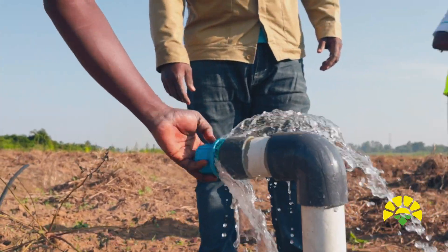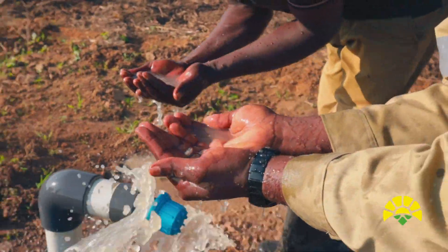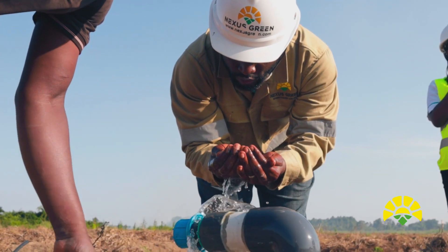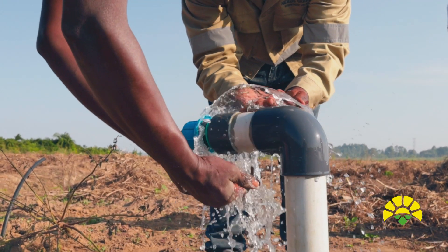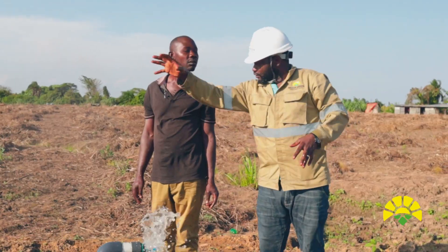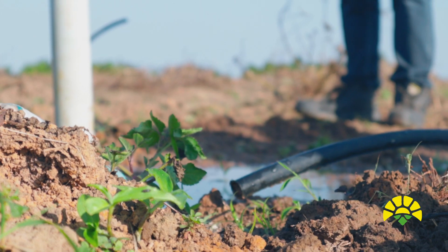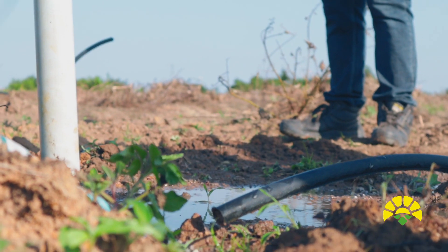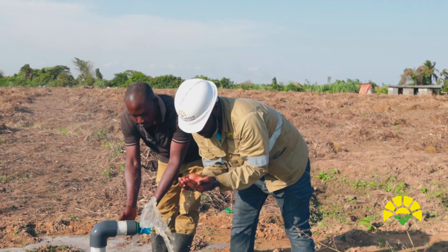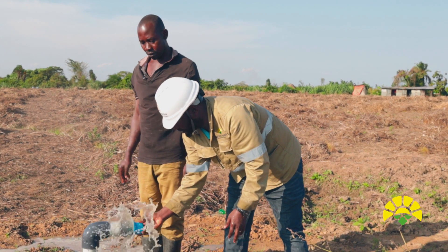As you open, you can look at the water and see what is there. Some of these things you see are because maybe the system was not flushed — so when they were storing, these things were going in there. The purpose of this flushing is that the system is washed clean and whatever is in there is thrown out. Every time you feel like you need to clean, you do it. You create your own program and run it for a few minutes until you see no dirt, then you close.